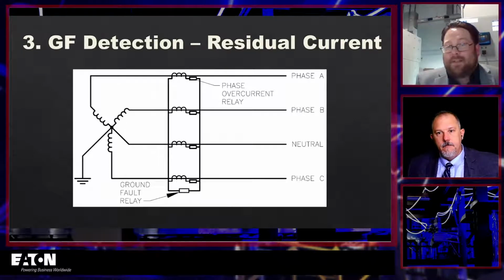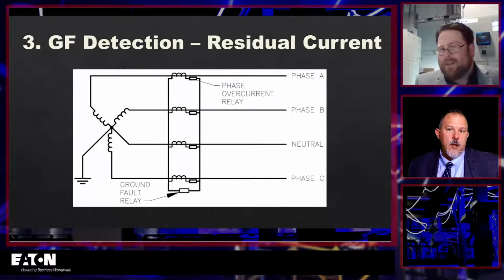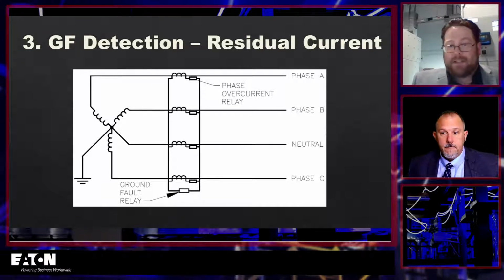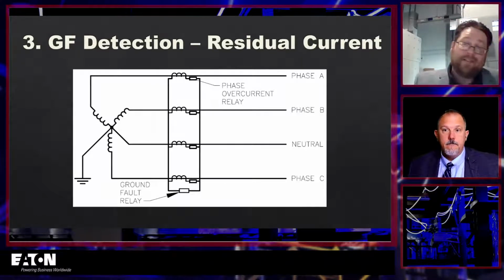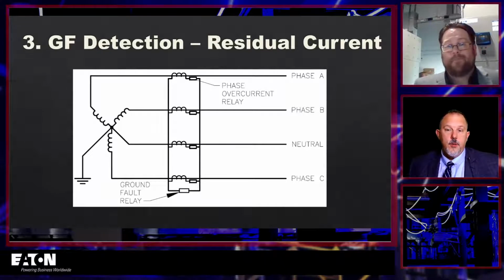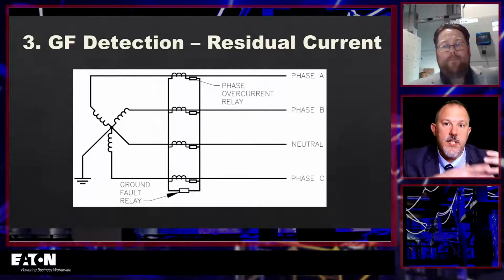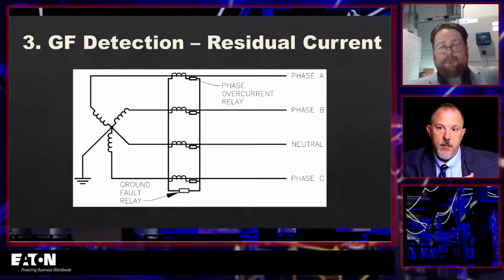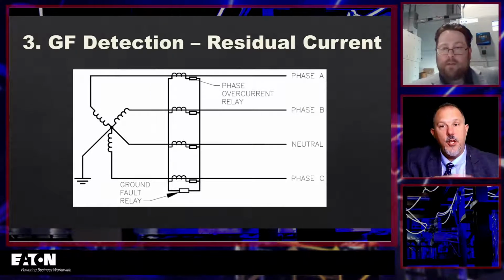I would potentially ask the utility what their upstream devices are on the primary side. This is a single service to that school. Potentially, you might be able to work something out with the utility where you sense ground fault and you trip their device. I don't know if that's really code. You could do that. It doesn't say it has to be the service entrance device on your side. It could be the utility side. Yeah, you would have to install some CTs somewhere downstream to sense that ground fault, and then you would have to shunt trip something.